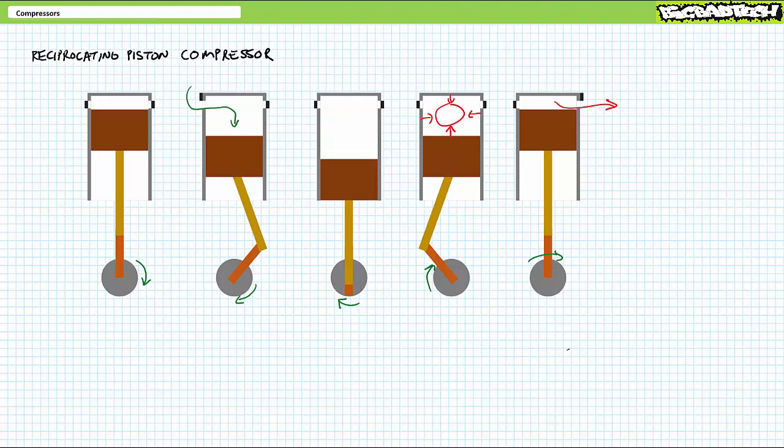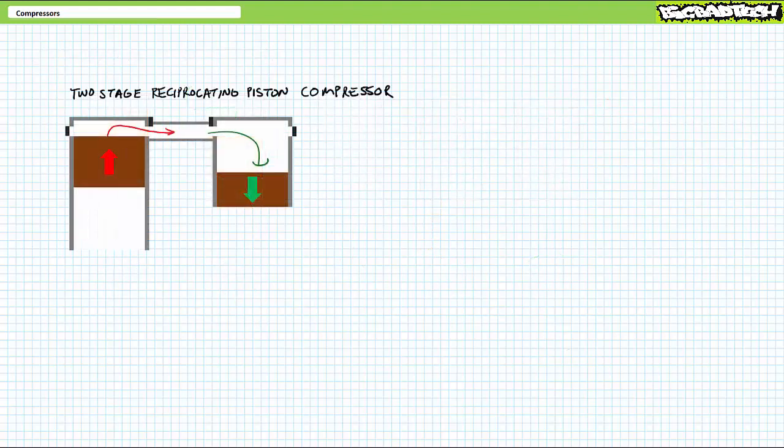What I've described is the operation of a single-stage reciprocating piston-style compressor. While single-stage compressors do exist, it's often more efficient to perform compression using more than one stage. Consider a two-stage reciprocating piston-style compressor driven by the same shaft. While the primary cylinder is in the compression stage with an open outlet, the secondary cylinder is in the suction phase with an open inlet. Previously compressed air from the primary cylinder is drawn into the secondary.